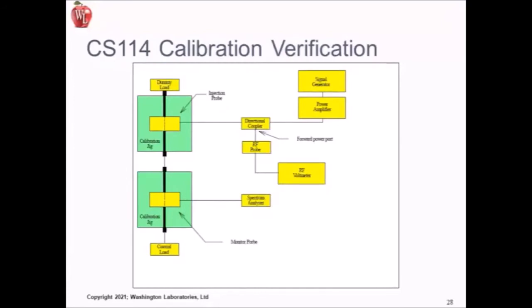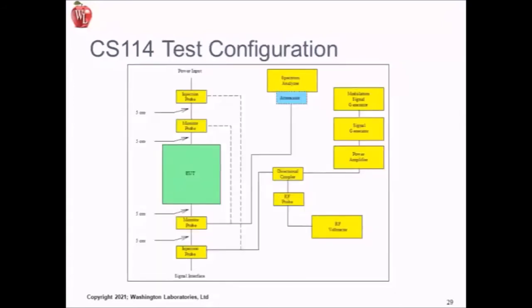And these are the two calibration verifications. So this is the actual test. So you have the equipment under test. You have certain distances where you have injection probes and monitor probes, and they're specified to be 5 centimeters away from the equipment at least.